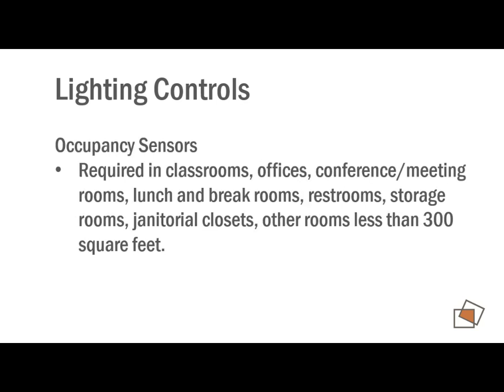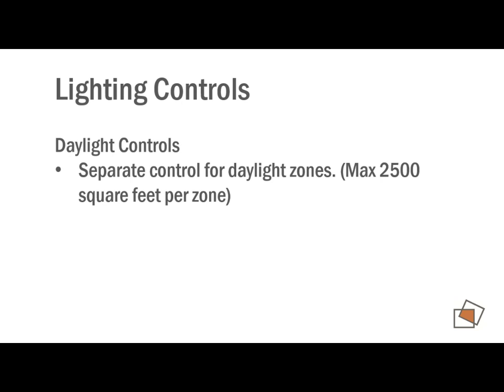Occupancy sensors are required in these types of spaces. Rooms less than 300 square feet is going to capture a lot of small rooms, but I'm sure you're used to putting occupancy sensors in many of these types of spaces. Like I said, this is not mandatory right now in Springfield. So if you still get the owner who insists that they don't want an occupancy sensor, then you can still leave them with the manual control. But this is becoming standard design practice in a lot of cases.